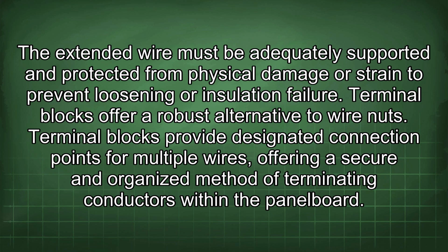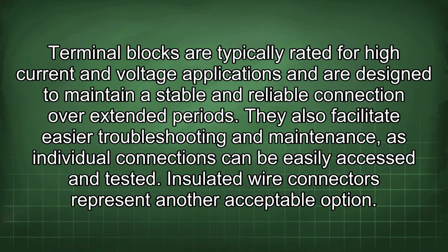Terminal blocks offer a robust alternative to wire nuts. Terminal blocks provide designated connection points for multiple wires, offering a secure and organized method of terminating conductors within the panel board. Terminal blocks are typically rated for high current and voltage applications and are designed to maintain a stable and reliable connection over extended periods. They also facilitate easier troubleshooting and maintenance, as individual connections can be easily accessed and tested.